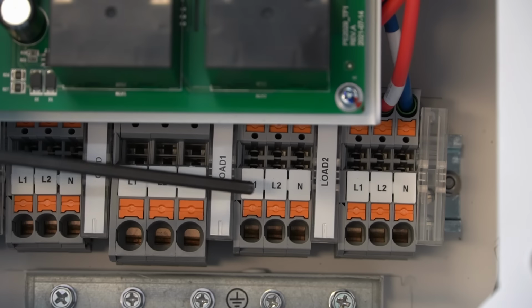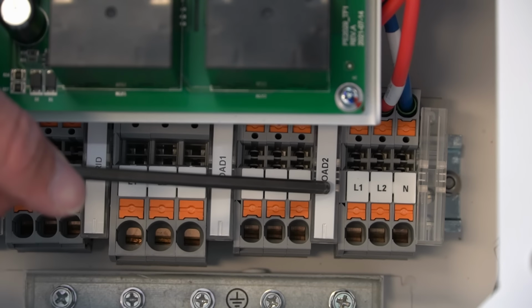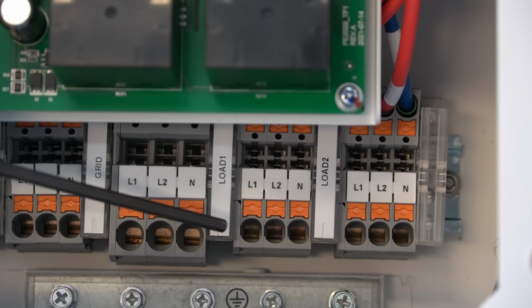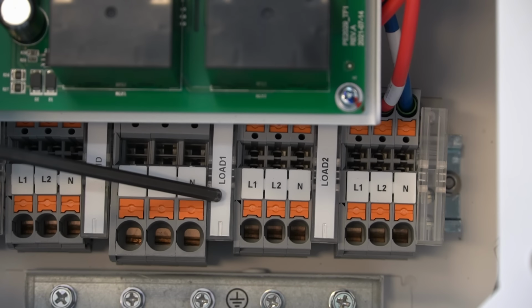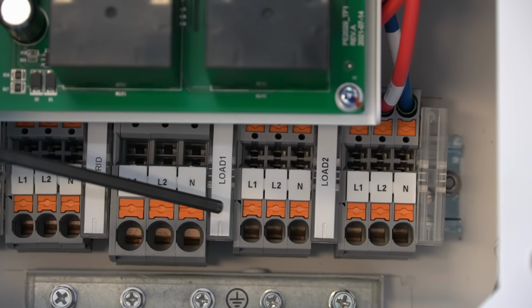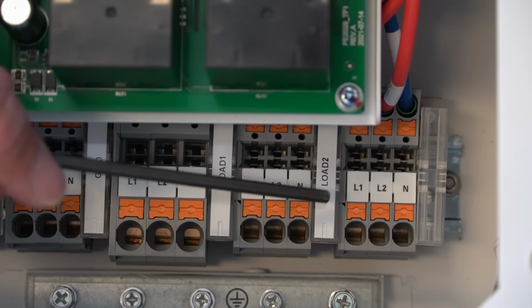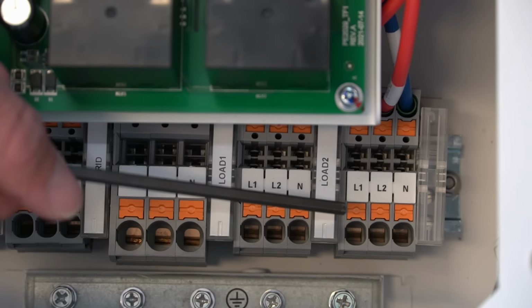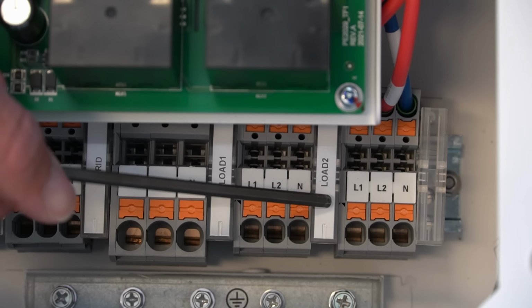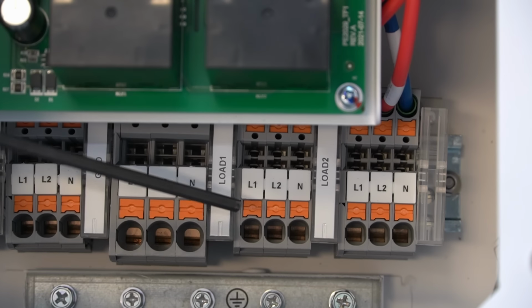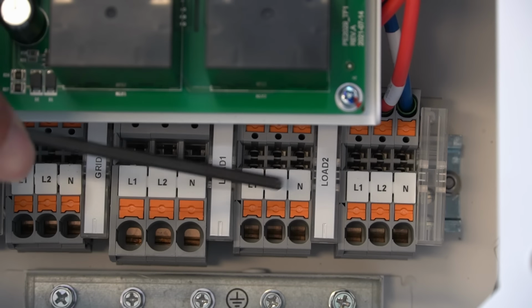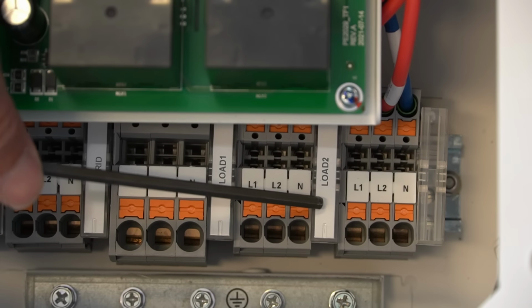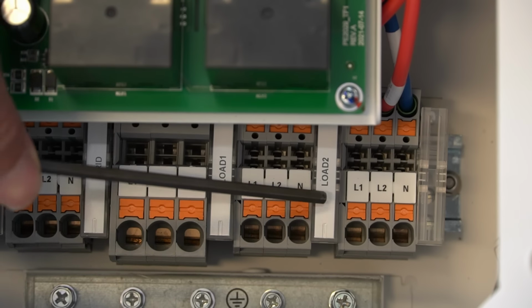Now you might be wondering, why is there a load 1 and a load 2? And that's because on this inverter, it has a special feature where load 1 is for critical loads only. If you're using this inverter for off-grid use only, you're going to want to connect all your loads to load 1. Load 2 is for not critical loads, and it will shut down if there is no grid connection or if the battery is insufficient. So for most people, you're going to want to stick to load 1 and ignore load 2, in my opinion. Now this feature is automatic, or you can trigger it manually.